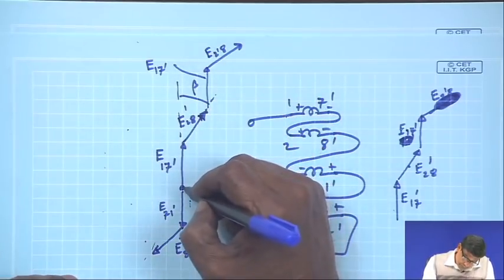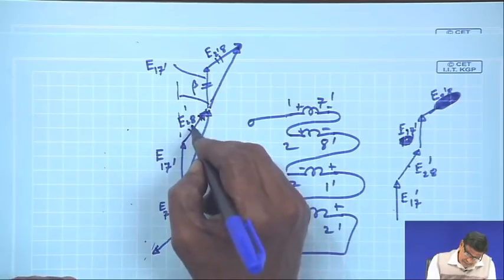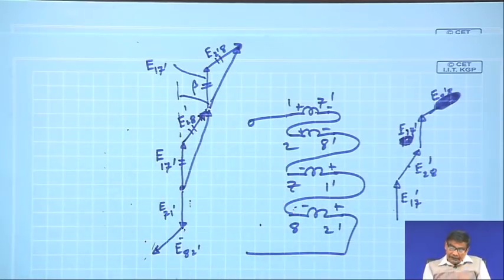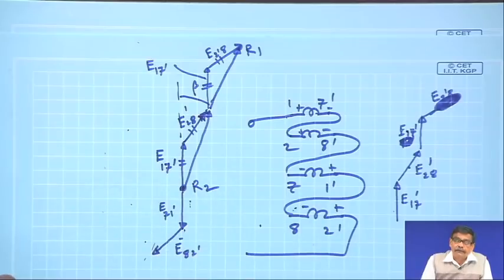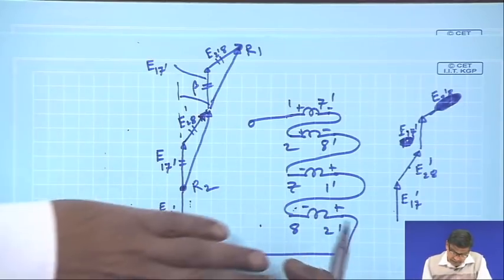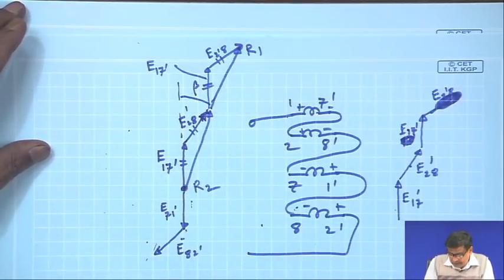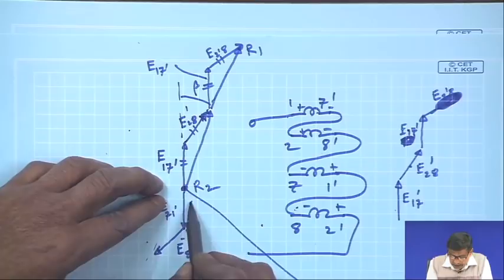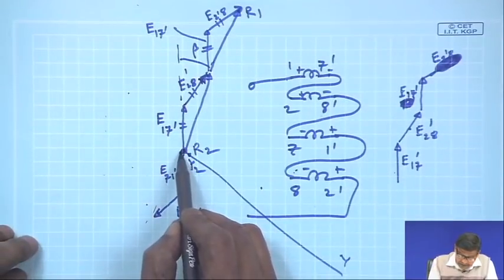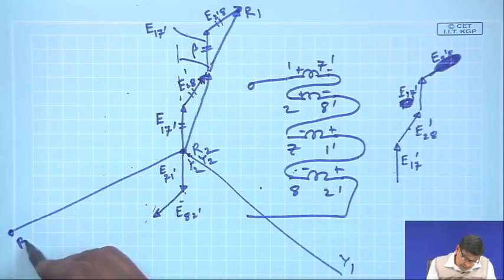And then this group voltages will be in phase, because the lengths of each one are the same. So, this will be the voltage between R1 and this is your R2. Understood? I mean, at this part I have reversed it, then added to the previous group voltages. So, this will complete R phase. Similarly, for the Y phase, those group voltages you add, and ultimately Y1 Y2 will be like this, and B phase will be B1 B2.